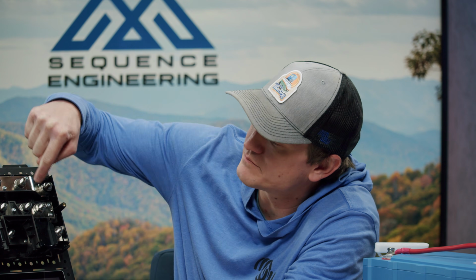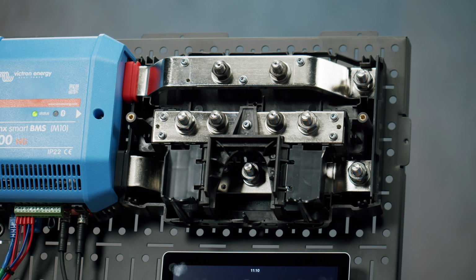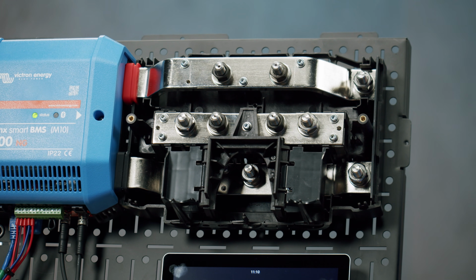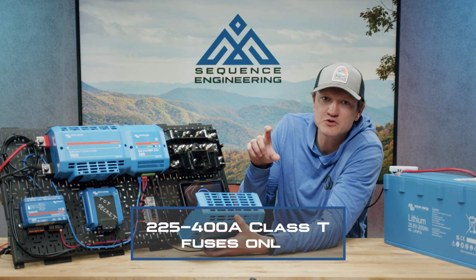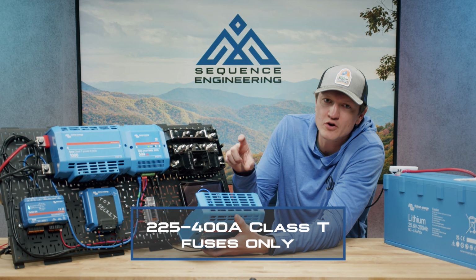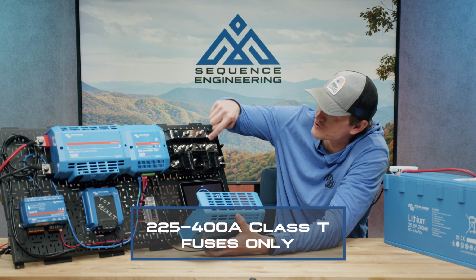One thing to note as you design and use the Class T, or the Lynx Class T Powerin, is that this bolt hole spacing here is specifically designed to operate inside of the Class T fuse that is 225 amps up to 400 amps. So you must purchase a Class T that is in that size range.